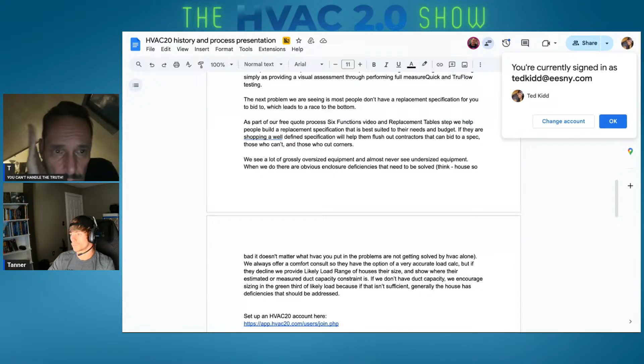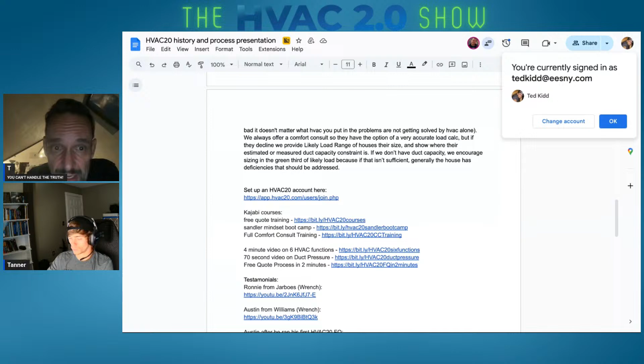We see a lot of grossly oversized equipment and almost never see undersized equipment. When we do, there are obvious enclosure deficiencies that really need to be solved. Sometimes it's so bad it doesn't matter what HVAC you put in, the problems aren't solved by HVAC alone. We always offer a comfort consult so they have the option of a very accurate load calc. But if they decline, we provide a likely load range for houses their size and show where their estimated or measured duct capacity constraint is. If we don't have duct capacity, we encourage sizing in the green third of likely load, because if it isn't sufficient, generally the house has deficiencies that should be addressed.